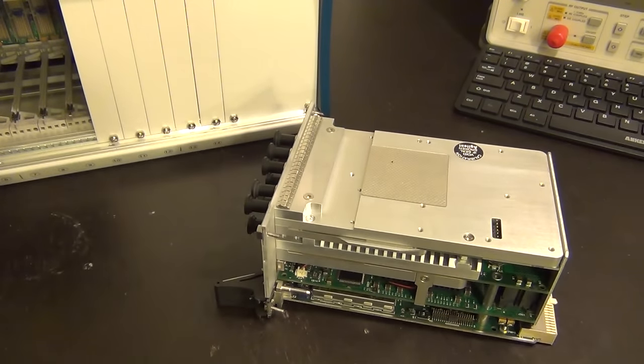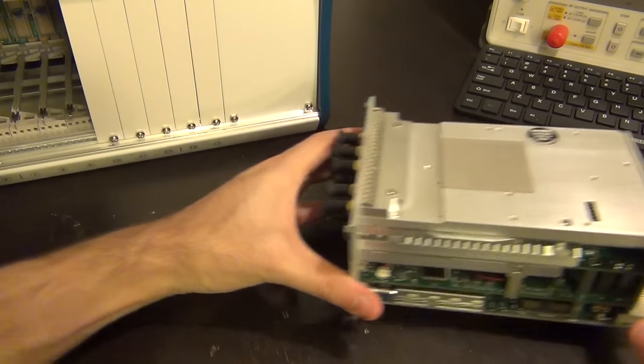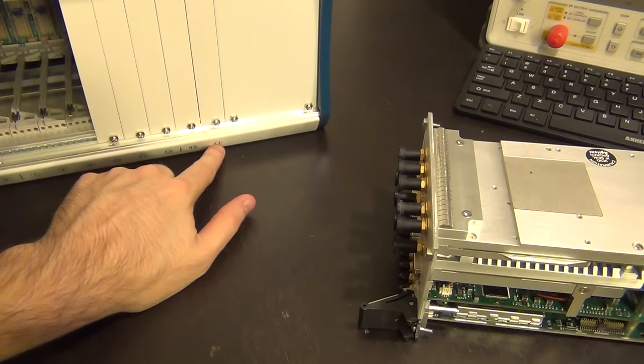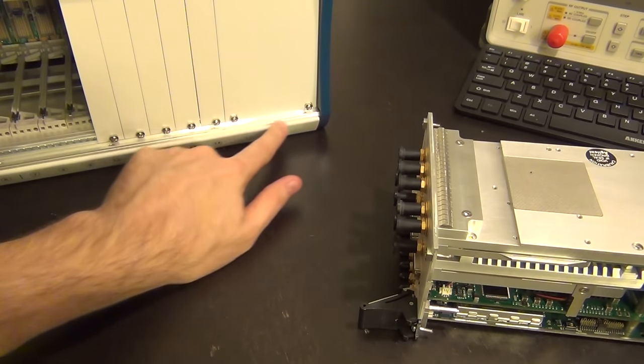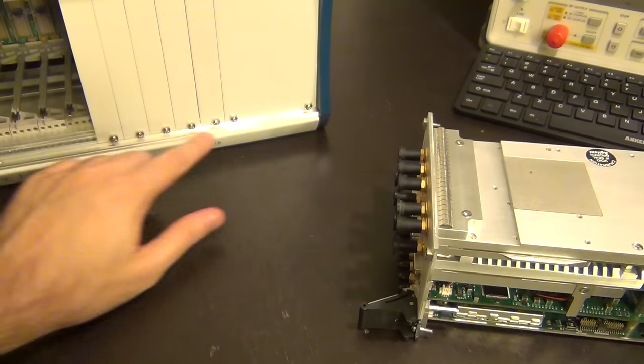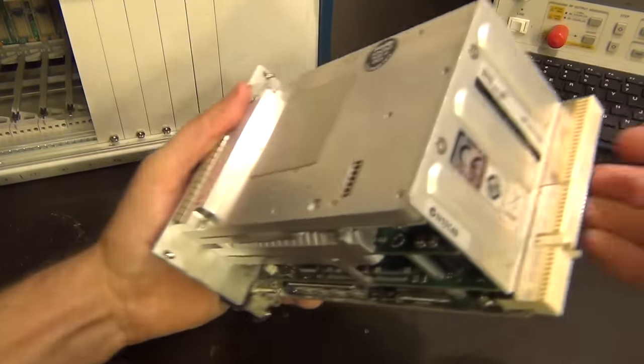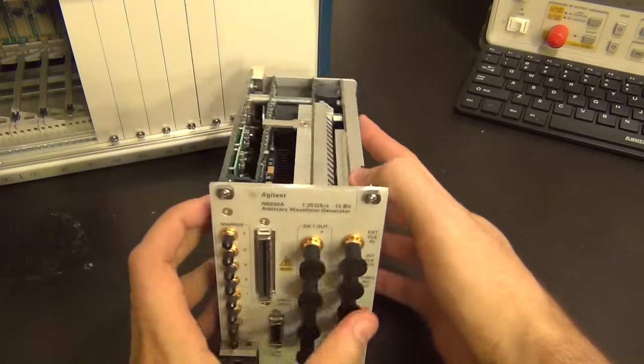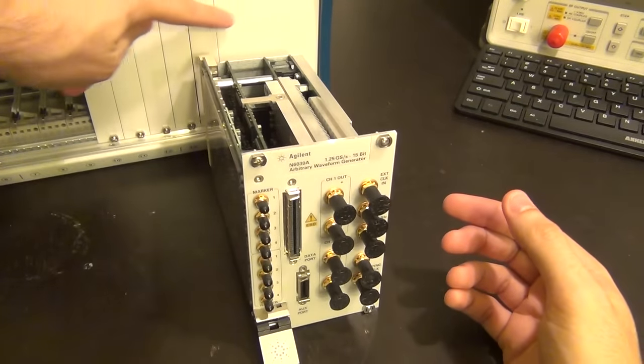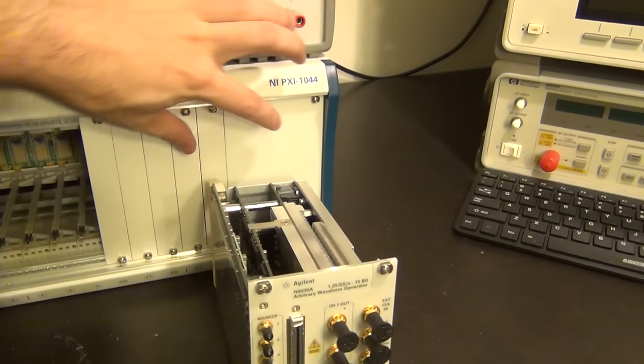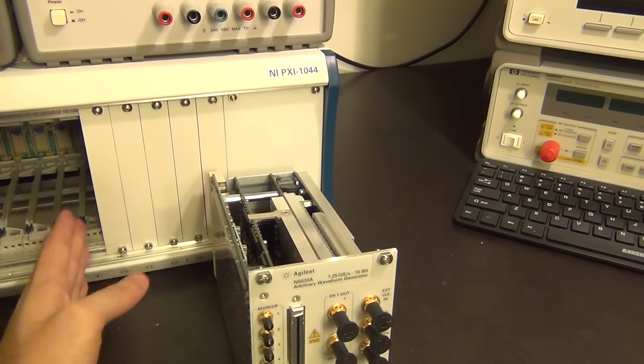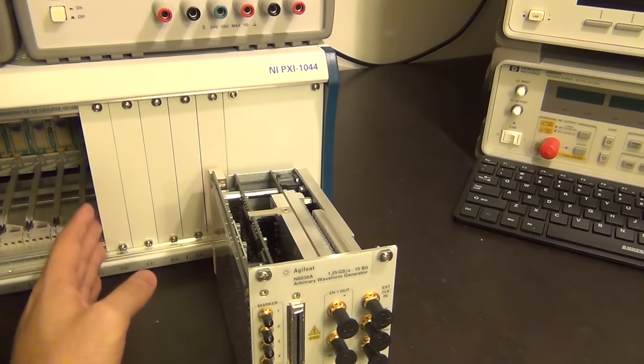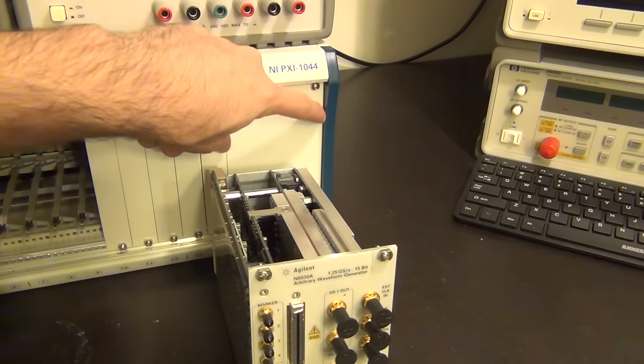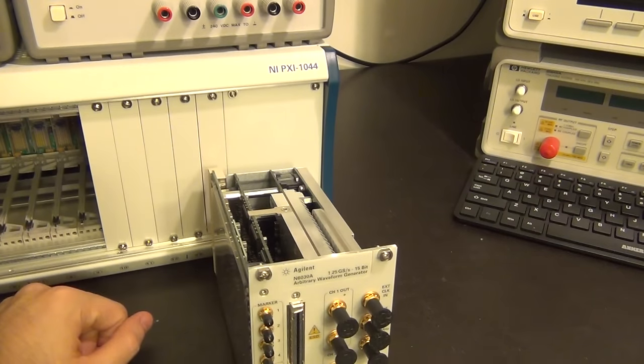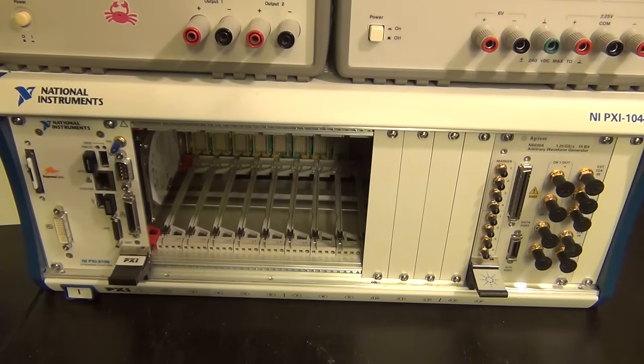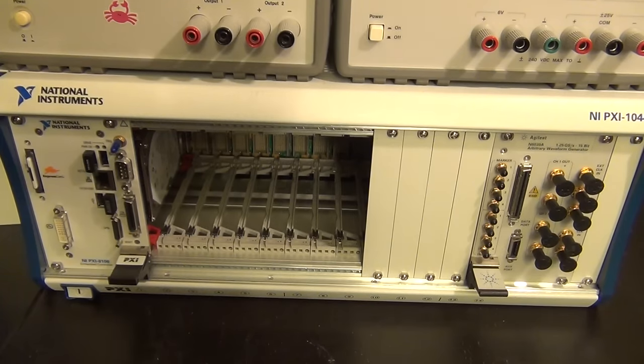Now, where I'm going to put this is at the very, very end. That's because the actual PXI connections end here in slot number 14, and there's no more connections to the motherboard. They're actually blank. They don't have the connectors installed. But if you look at the way this is, the connector is all the way here. If I were to install it in this point here, it will occupy multiple slots which have connectors which can be used for other PXI modules. But installing it at the end allows me to save unused slots like that. So let's go ahead and put it in. All right, two down, a whole bunch more to go.